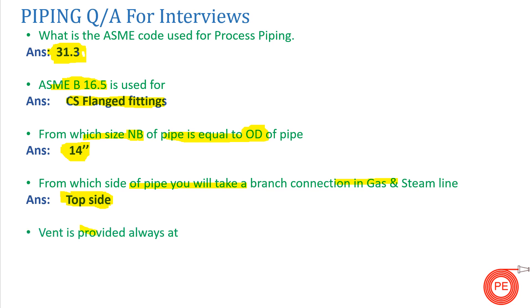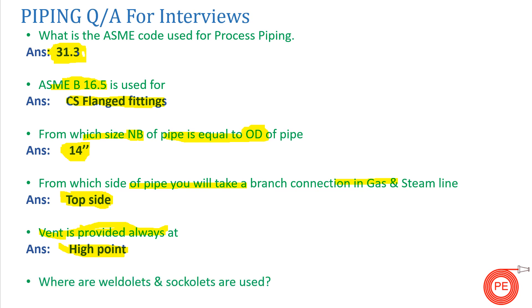The next question is: where is a vent always provided? The vent is always provided at the highest point, so that all gases trapped in the pipe can be released to the open atmosphere. If the vent is not at the highest point, gases may remain trapped. Similarly, the drain is always provided at the lowest point.